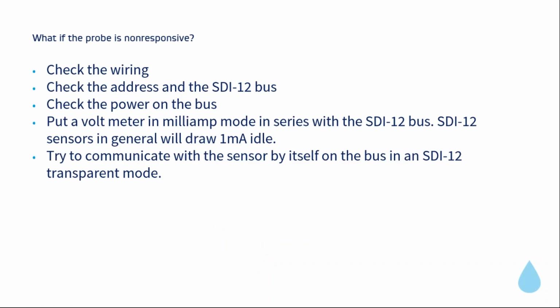Some other things about the field: if you have a probe that's non-responsive, you can check the wiring. Of course, double check the address. With your voltmeter, you can check the power of the bus—most SDI-12 buses are 12 volts, supplied from the logger.